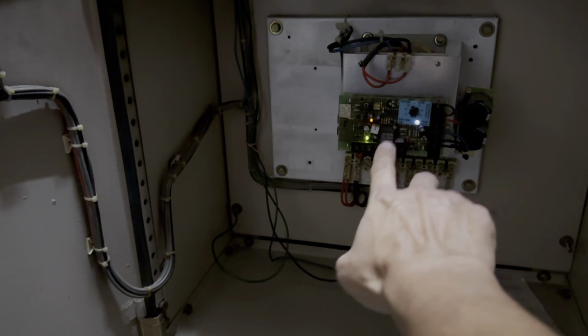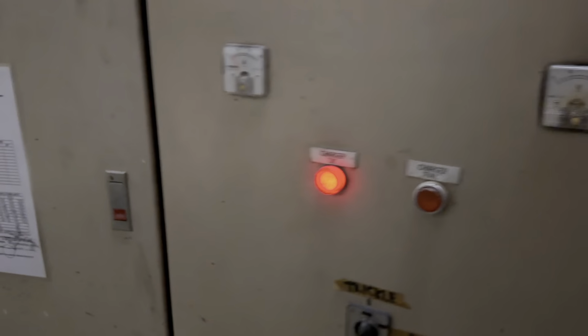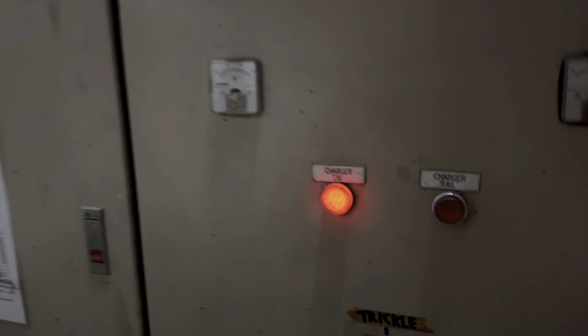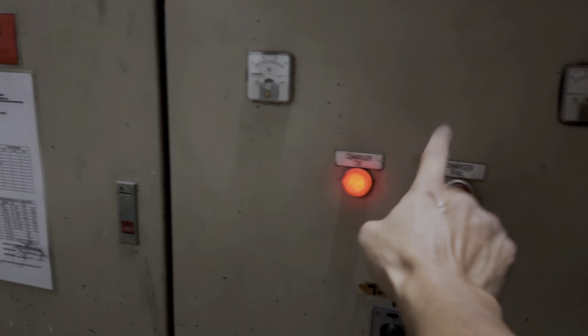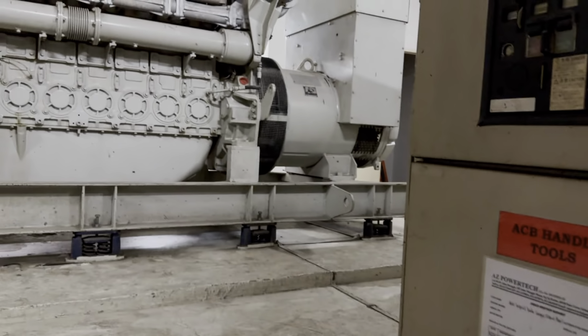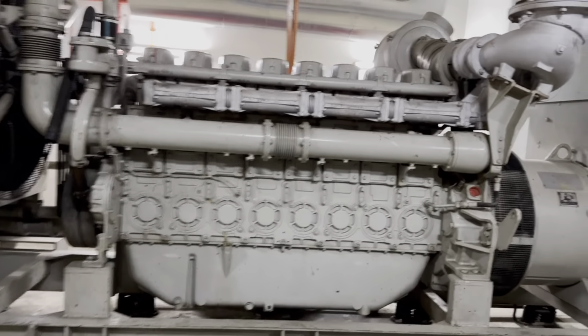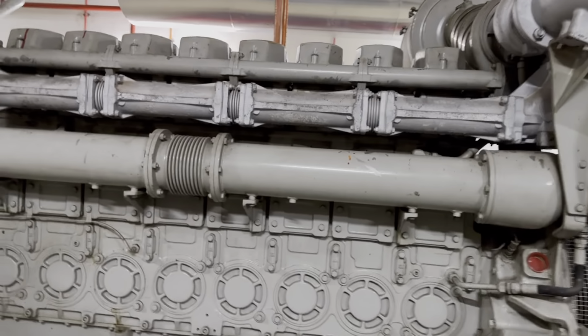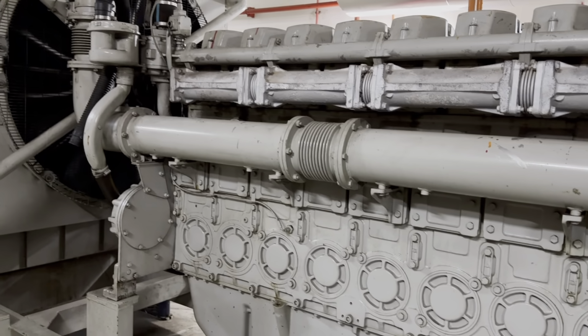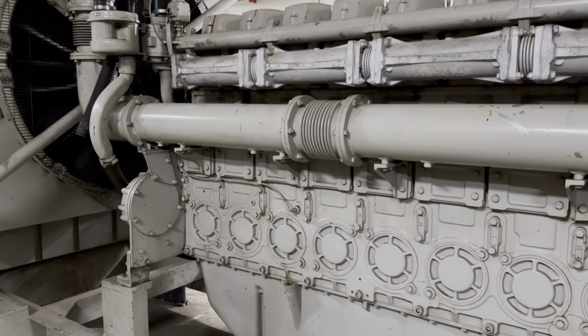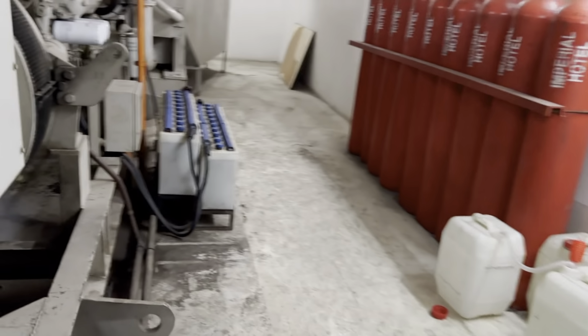Normally, all gensets have a genset AMF panel battery charger. So this charger will charge the battery during idle, when the genset is not running. As the genset is in operation, the alternator of the genset will take over and charge the battery. What happens if the alternator fails and doesn't charge the battery?